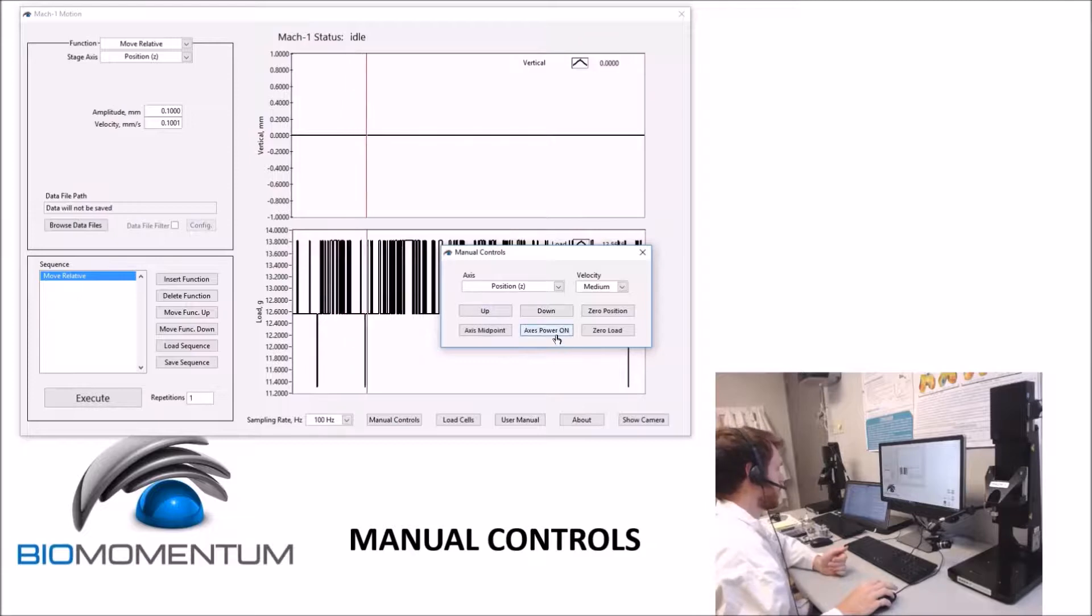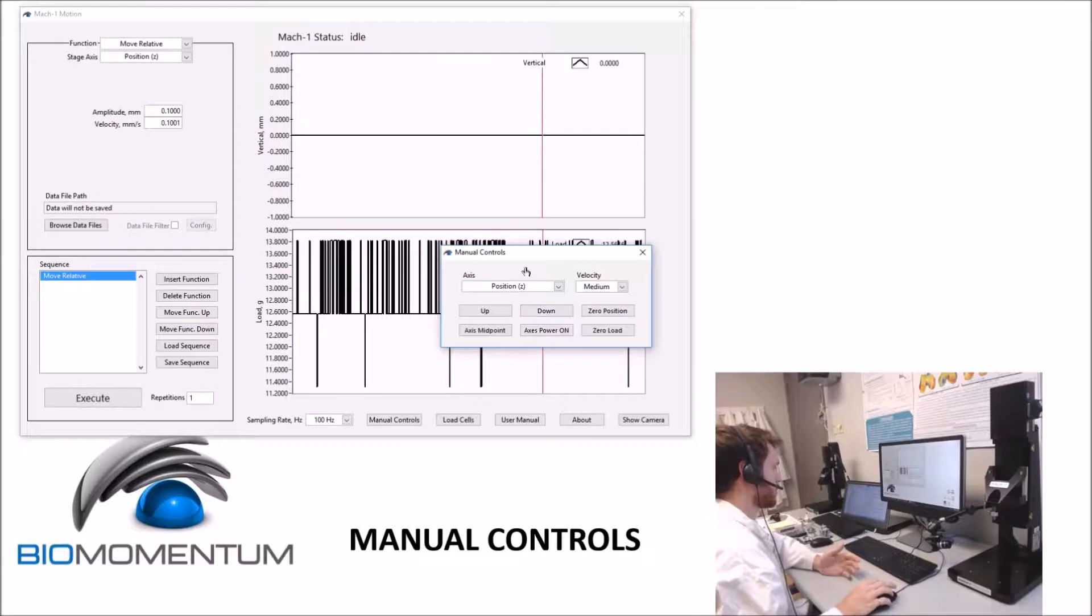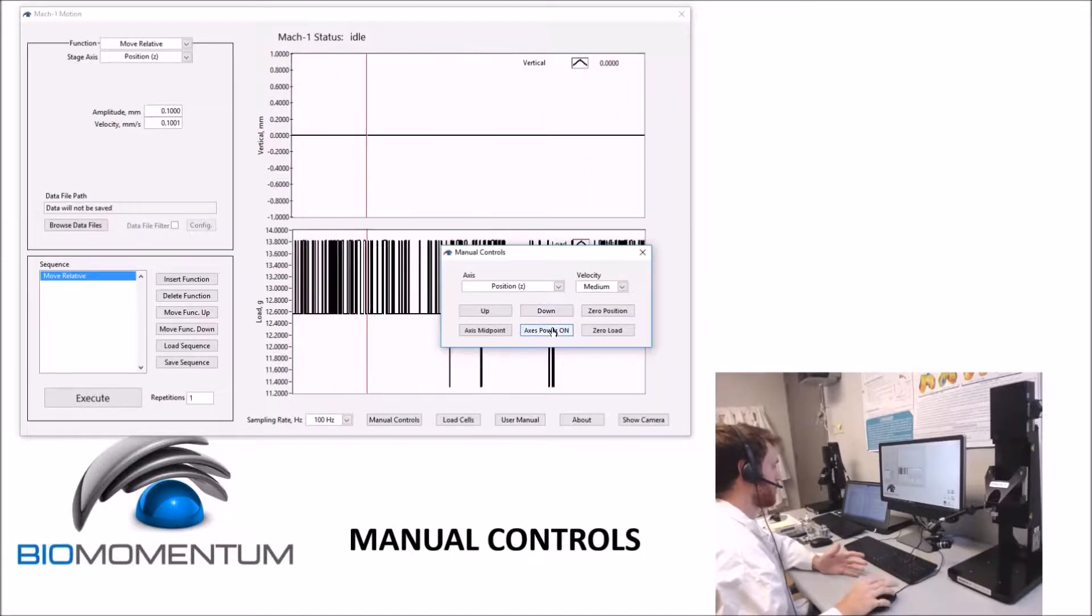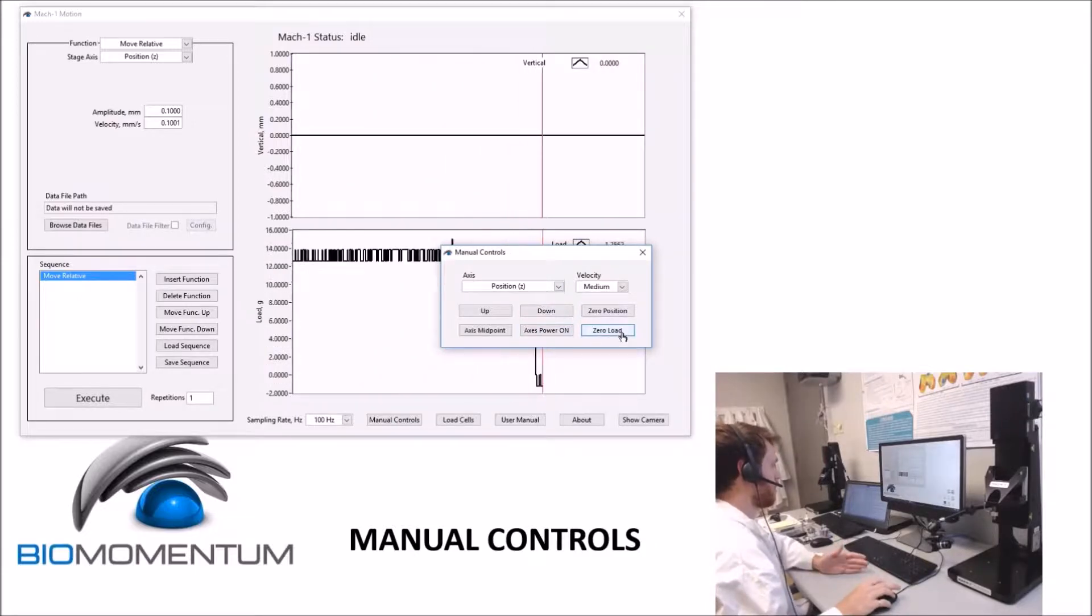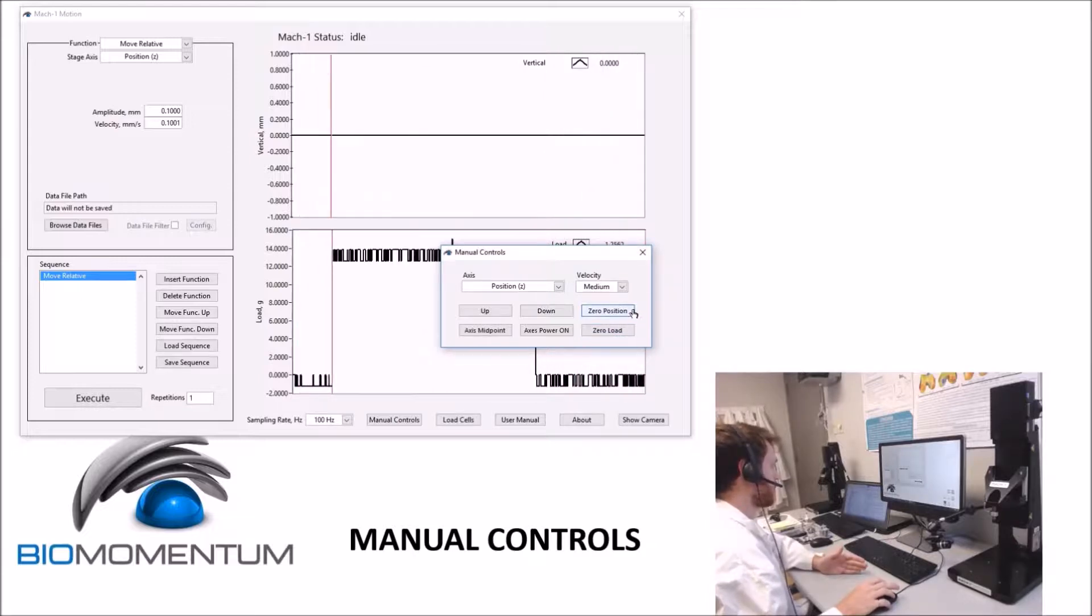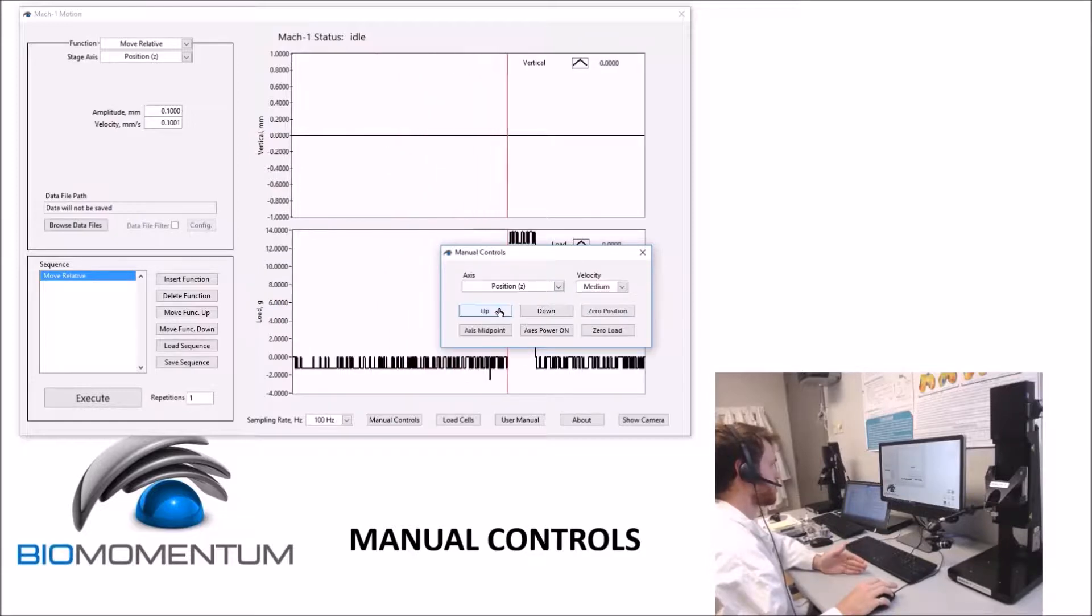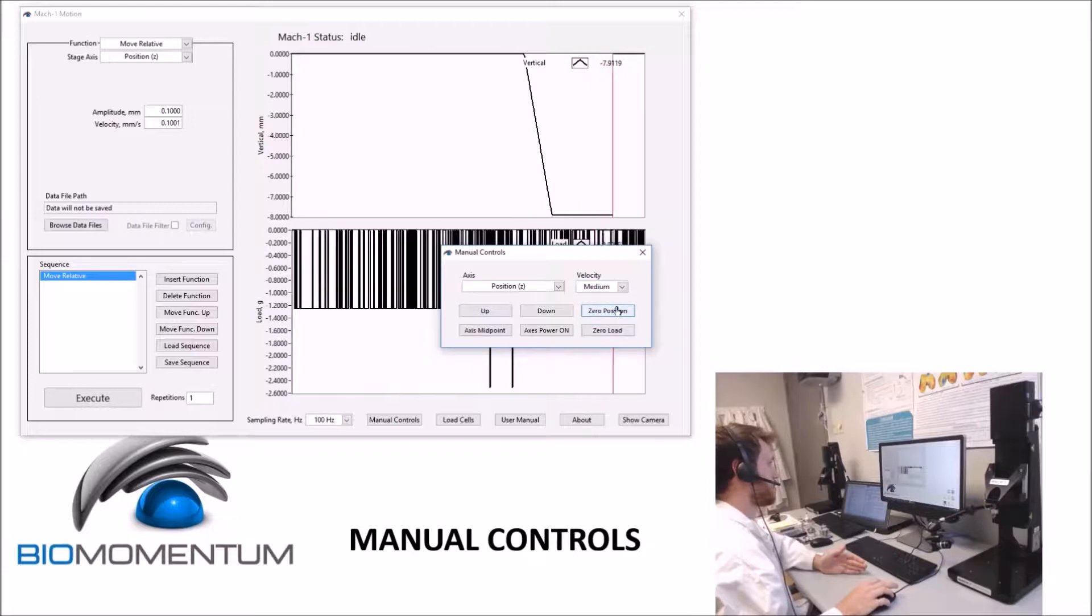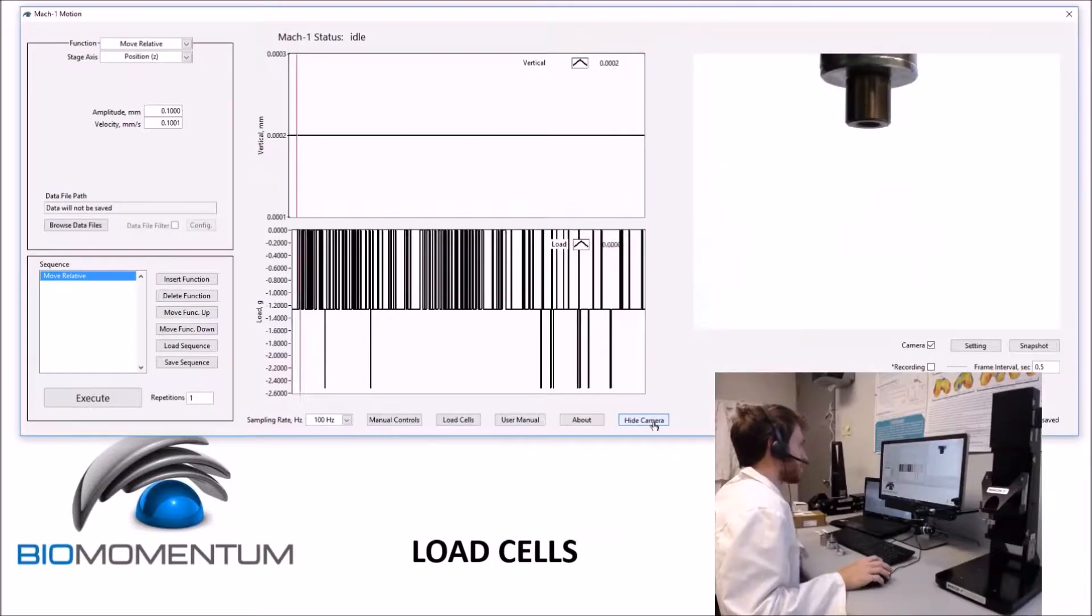Clicking the Axis Power On button will turn the stage motor on corresponding to the axis. This may be required after overload detections or upon receiving errors from the motion controller. Clicking the Zero Load button will set the current load read by the load cell back to zero, and on multi-axis systems all load components will be zeroed at the same time. Clicking the Zero Position button will set the current position read by the selected axis as the new zero. We'll use the camera to clarify this next part.